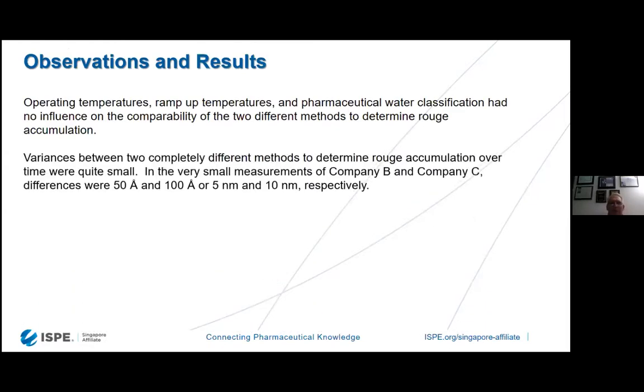Operating temperatures, ramp up temperatures, pharmaceutical water classification had no influence on the comparability of the two different methods to determine rouge accumulation. It didn't make any difference whether we were doing Auger or doing online rouge monitoring. But Auger, again, is a destructive test. You have to take into consideration that.